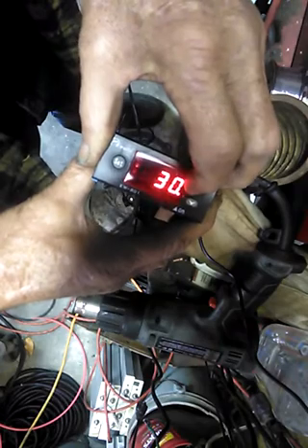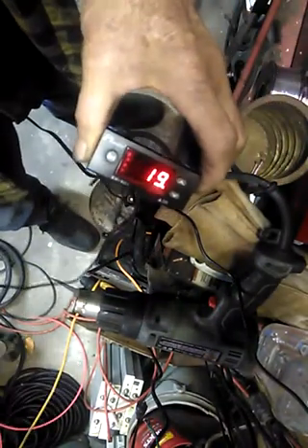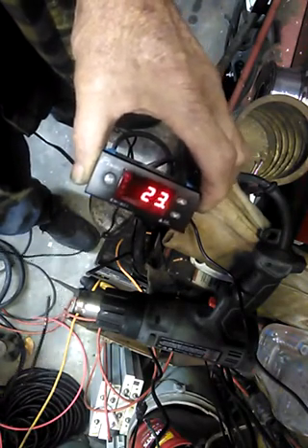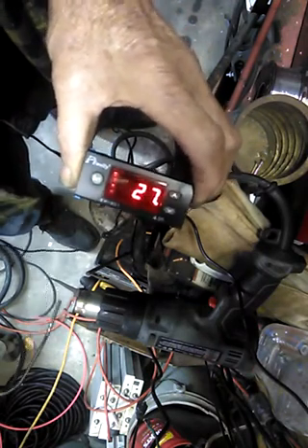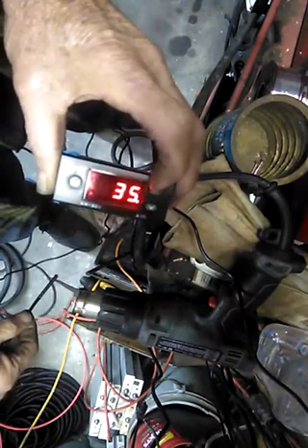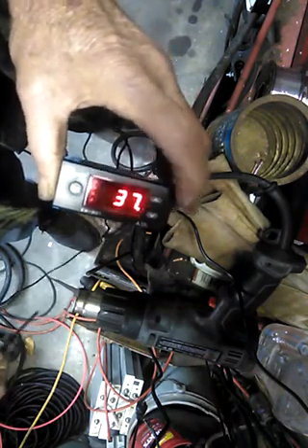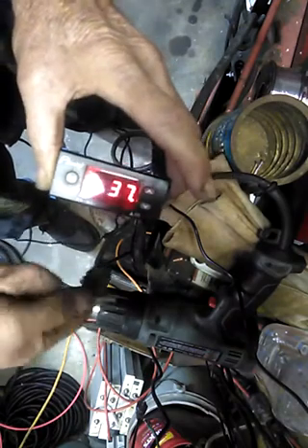The temperature is going down. Now, when this gets by the other side, I'm going to heat up my other probe. And you see that number is going up. And when it gets past the other number, we should see that little dot disappear, which will be a sign that the relay has changed. We're not seeing anything right this minute. 23 and 37 — yeah, we should have flipped over. But we didn't.